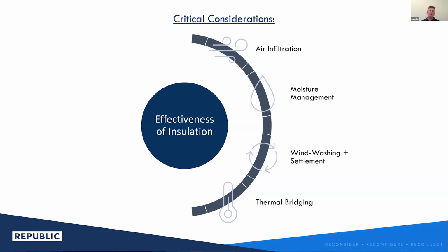Because I think Andrew touched on it here, there's effective R values. And I think most of what we're looking at in terms of compliance-based modeling isn't really a full understanding of what the effective R value is. We're starting to see that change a little bit more as thermal bridging analyses and thermal bridging factors get dialed in and understood.